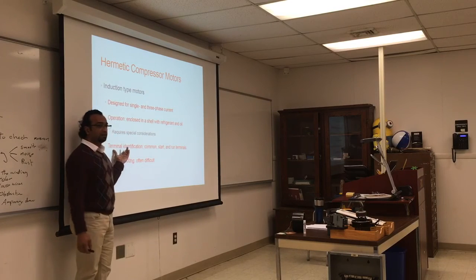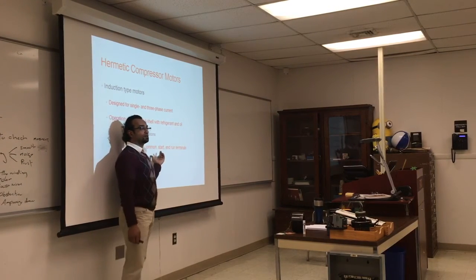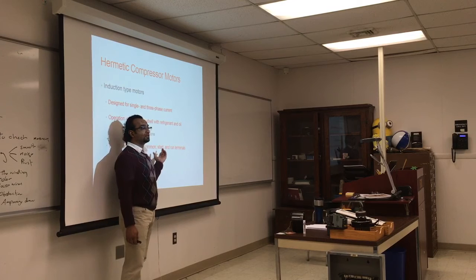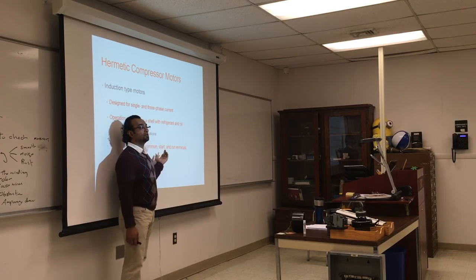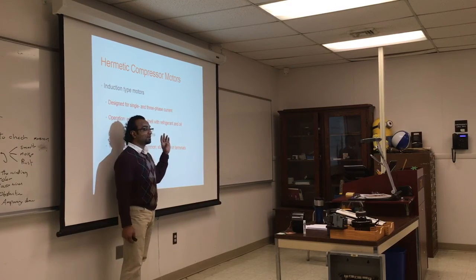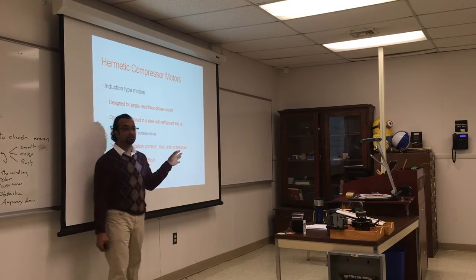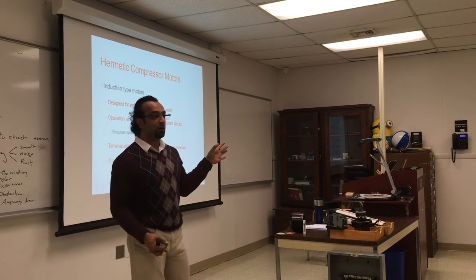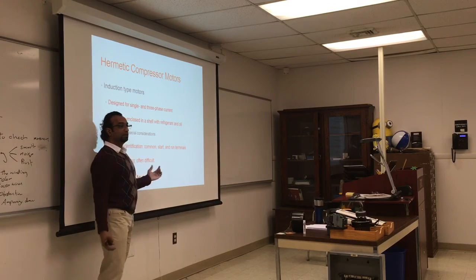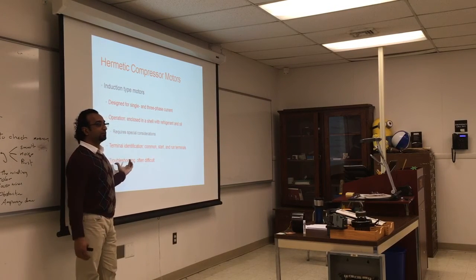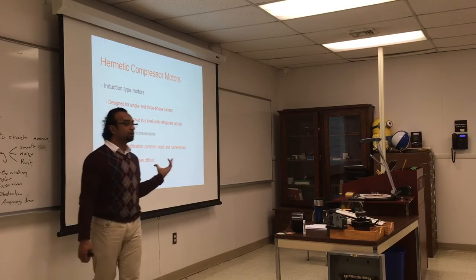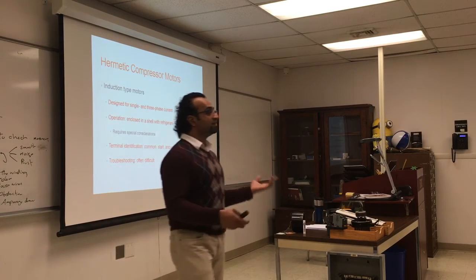So you want to identify the terminals. What would you find at the outside? The startup capacitor, startup relay, startup resistance. There's always some kind of way from the outside of the compressor to enable the startup winding and cut off the startup winding. Troubleshooting, you only deal with the outside, you don't deal with anything from the inside, and you just want to make sure that this is the problem.